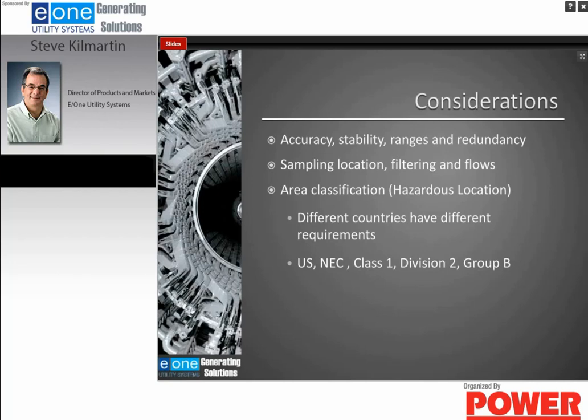The sample location of where the hydrogen sample is coming from the generator is, again, very important. We discussed it a little bit when I showed you that P&ID. We will discuss it again when I discuss purging the generator. You want to have filtering on it, again, to keep moisture and oil from entering the sensor. And you want to put it in a location where the flow is going to give you a representative sample of the hydrogen in the case, and that this flow is not interrupted.